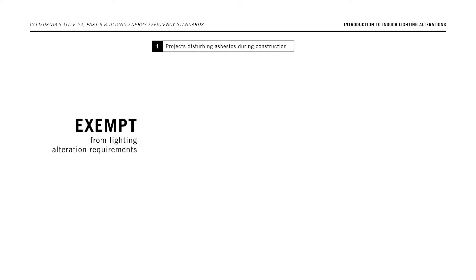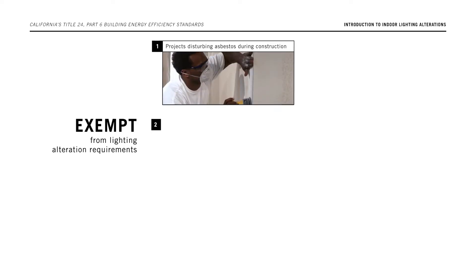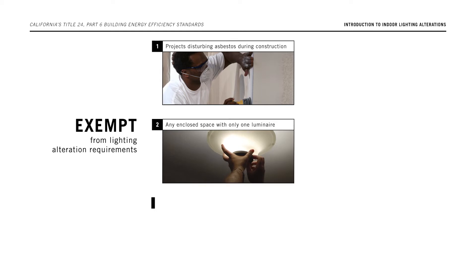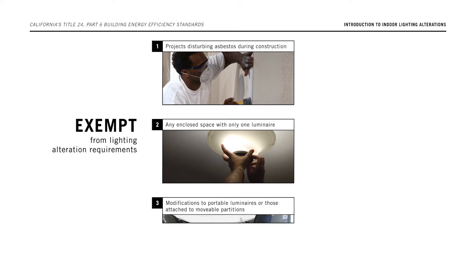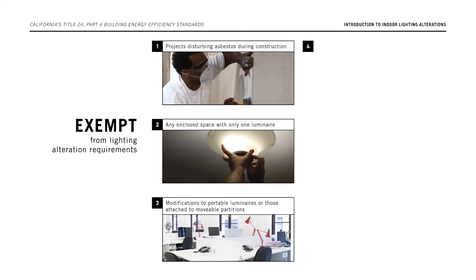Note that there are six types of projects that are exempt from the alterations requirements for indoor lighting. They include projects that could disturb asbestos during construction, any enclosed space with only one luminaire, and modifications to portable luminaires or those attached to movable partitions.